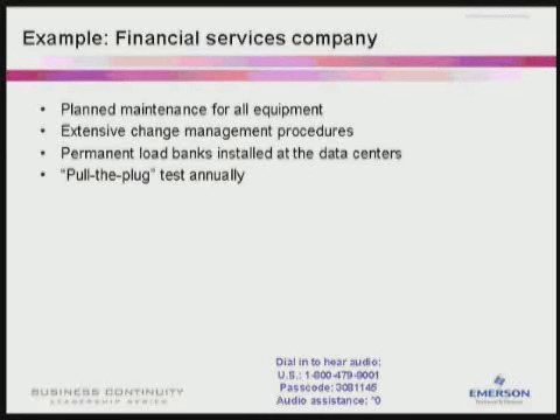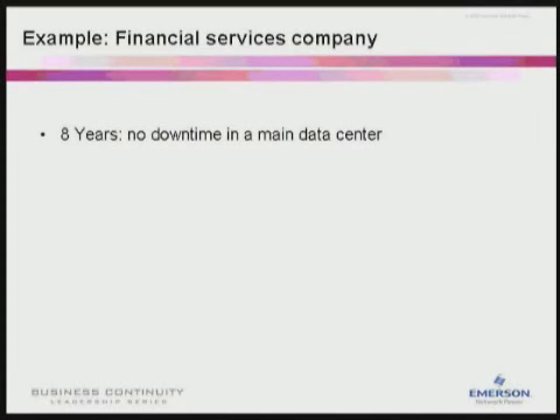Most large companies have load banks brought in to test generators once or twice a year, but this organization has load banks on site for frequent testing. Once a year, pull-the-plug testing is performed that sends all IT systems to backup generator power. Why is all this done? No downtime. The company's vigilance has paid huge dividends. In 8 years, it has experienced no downtime in any of its main data centers. This accomplishment is far above industry average, and the company has been able to capitalize on its reliability, and they promote it as a competitive advantage.